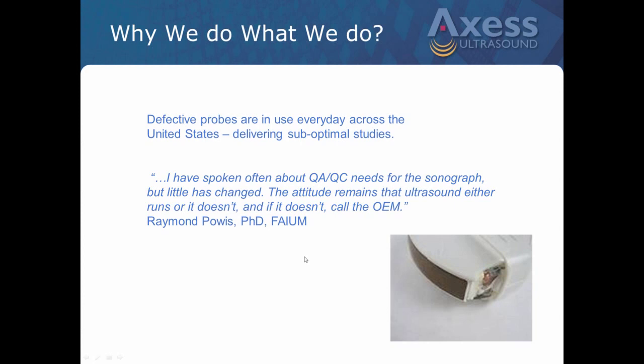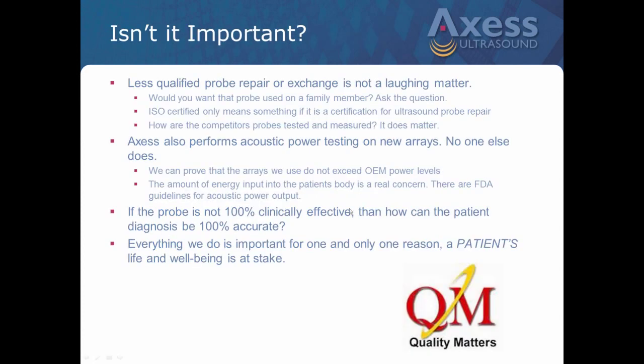Just a little statement from Dr. Powis. Defective probes are in use every day across the United States, delivering suboptimal studies. This statement right here, the attitude remains that ultrasound either runs or it doesn't. If it doesn't, call the OEM, is certainly not accurate. You can have a degradation in ultrasound or problems, as I hope I've shown, that are causing you clinical issues. So it's not just a matter of it breaks or it doesn't. So we've got to be on top of that by testing and looking after our probes.